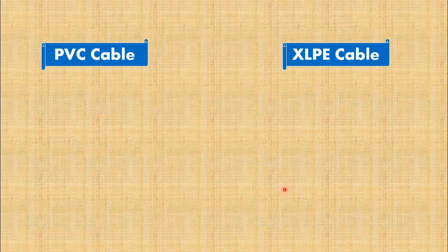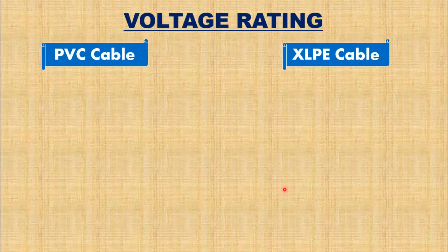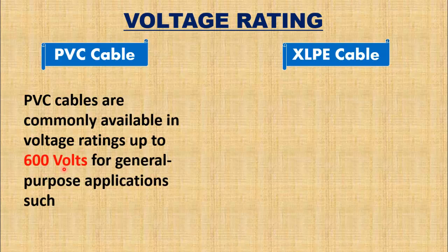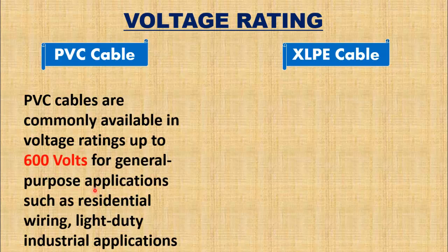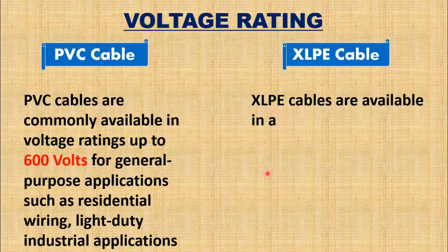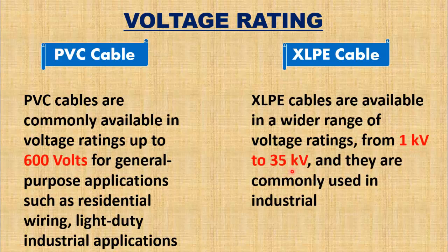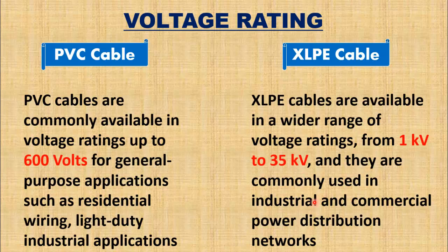Another difference is based on voltage rating. PVC cables are commonly available in voltage ratings up to 600 volts, and are used for general-purpose applications such as residential wiring and light-duty industrial applications. XLPE cables are available in a wider range of voltage ratings, from 1 kV to 35 kV and above, and are commonly used in industrial and commercial power distribution networks.